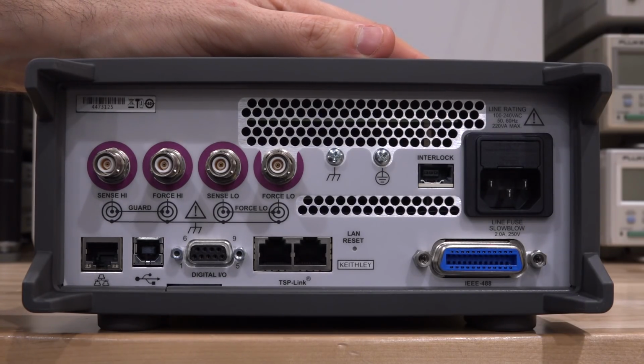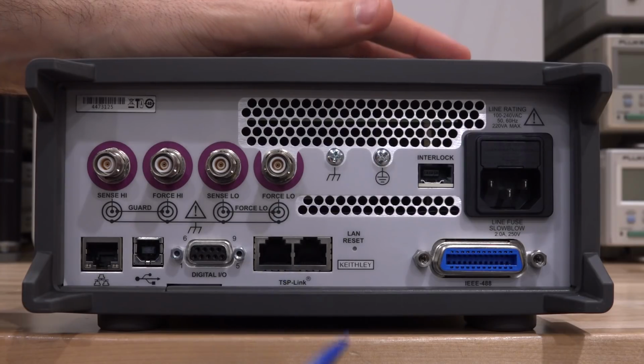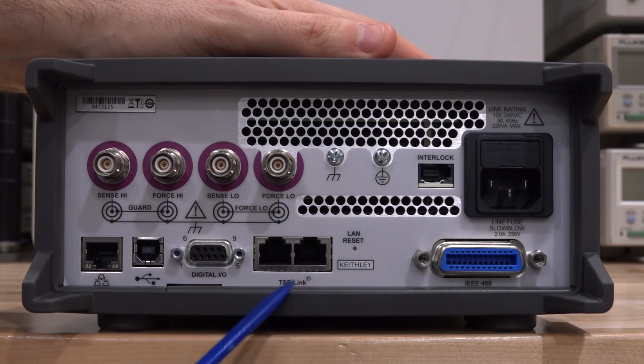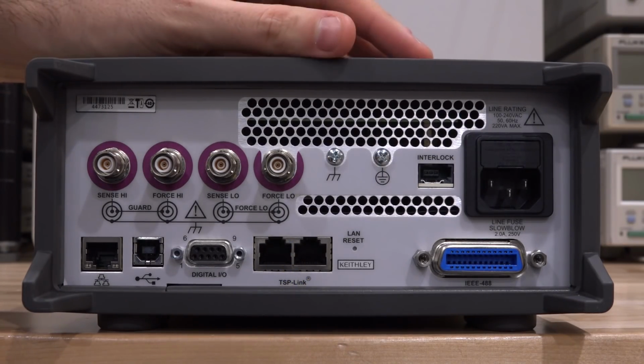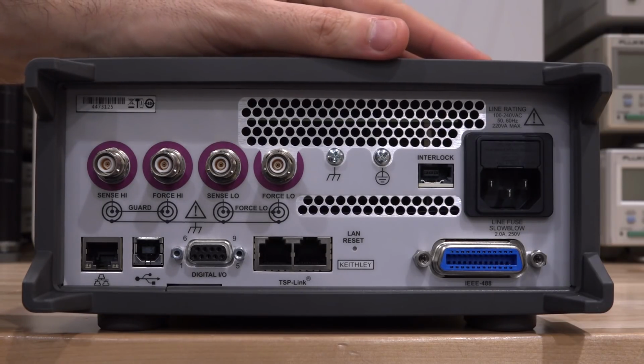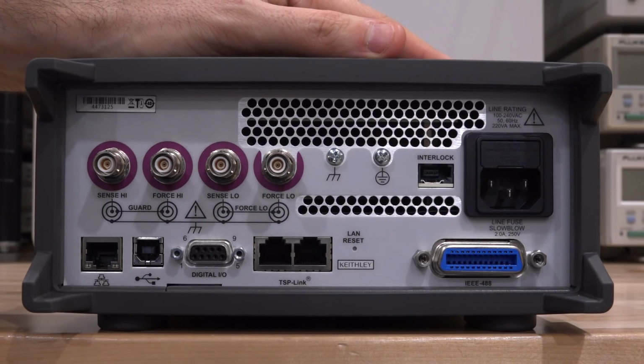But really my favorite interface here is the TSP link, not just because it spells the signal path, but because the TSP link allows you to daisy chain a variety of these instruments to each other, with a master instrument controlling everything else down the chain. So you only have to have one unit connected to a controlling PC, and all the other units in the TSP chain are simply connected together and work the same way.